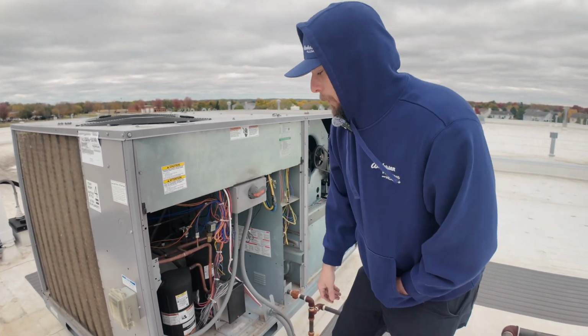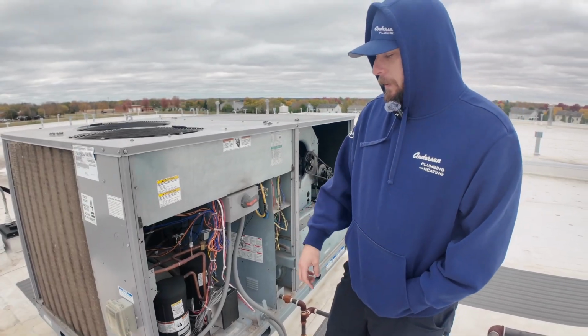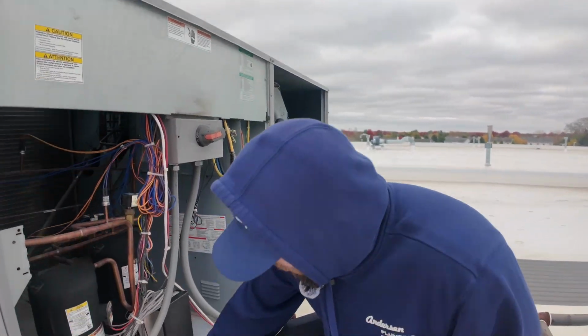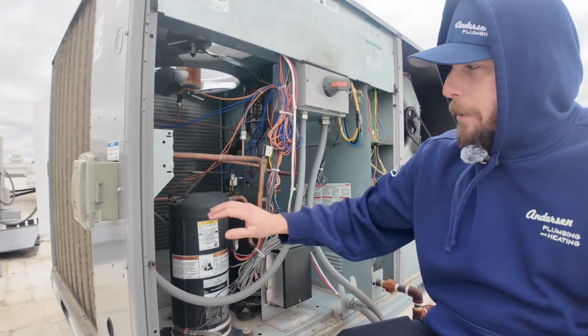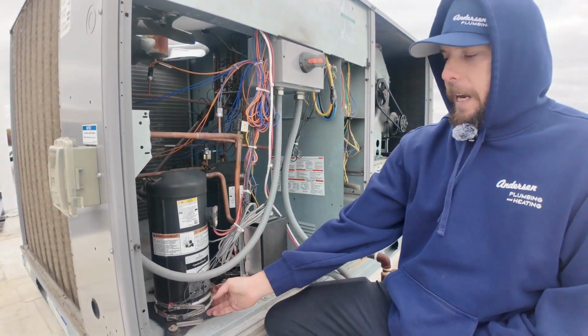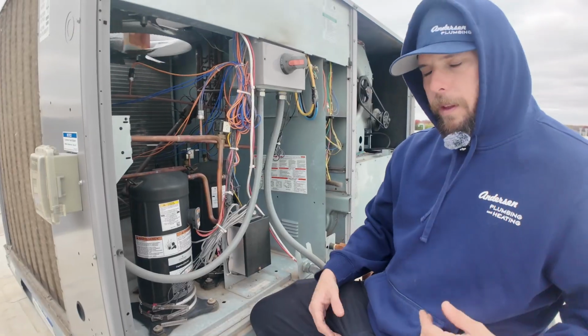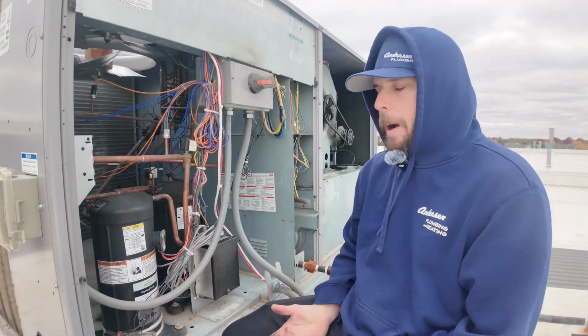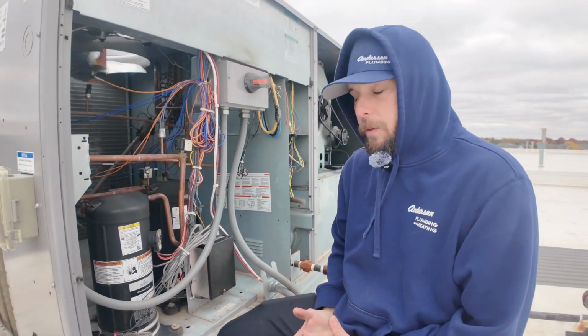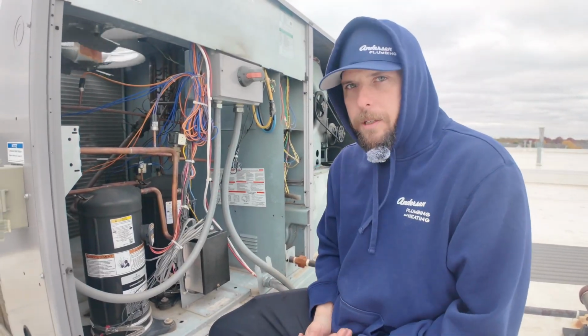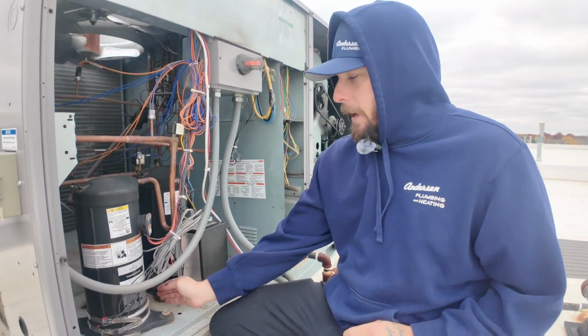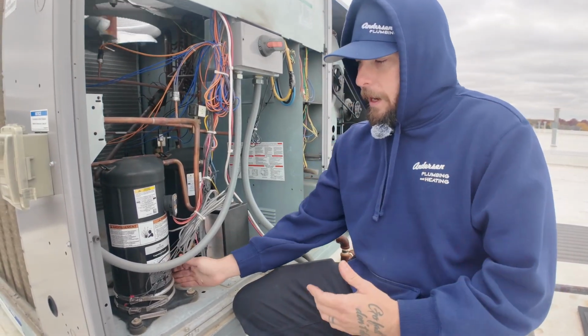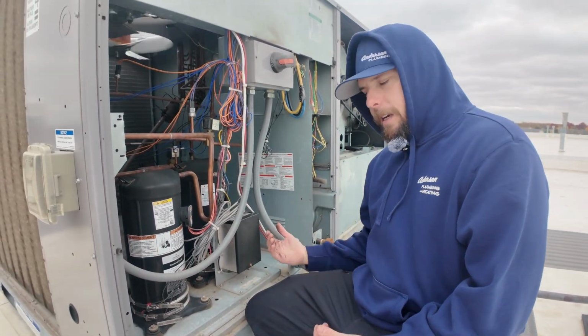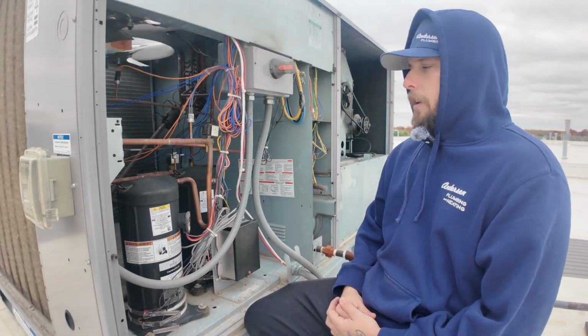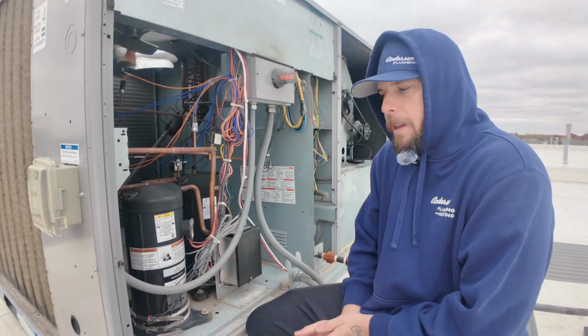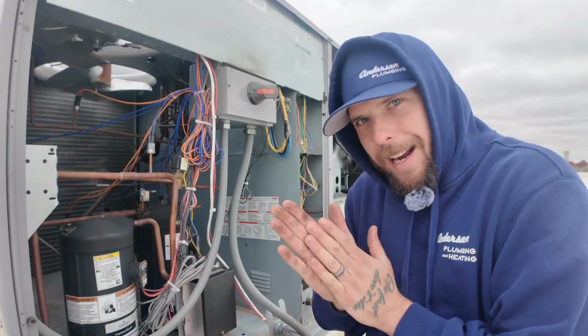So one of the other things we spoke about on the other side was the heater on the compressor. These bands that are wrapped around the bottom of the compressor, that's the heater. So what these do is they help keep the oil that's in the refrigeration system at an operable temperature, because when it's too cold, oil gets really thick, and that's how it can cause compressor damage. So between having this stuff so you can run it in a low ambient situation, the economizer, you know, that's how you're able to run these things when it's like it is today out.